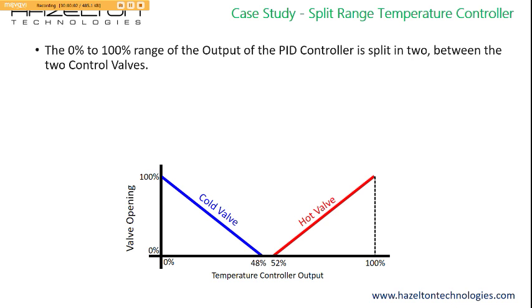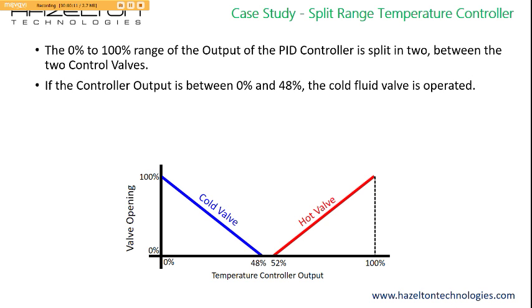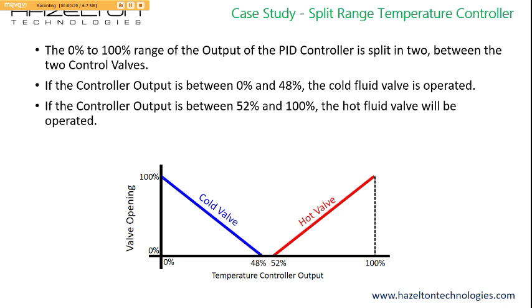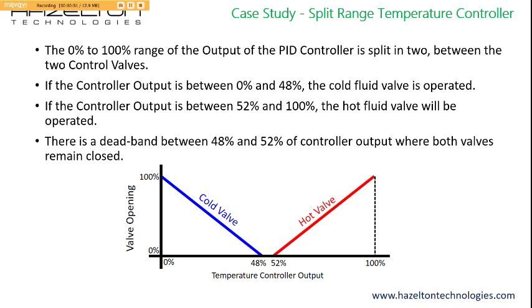The 0% to 100% range of the PID controller output is split between the two control valves. If the output is between 0% and 48%, the cold fluid valve is operated — fully open at 0% and fully closed at 48%. If the output is between 52% and 100%, the hot fluid valve is operated, starting to open at 52% and fully open at 100%. There is a dead band between 48% and 52% where both valves remain closed, to prevent seat wear from the controller constantly switching between the two valves.